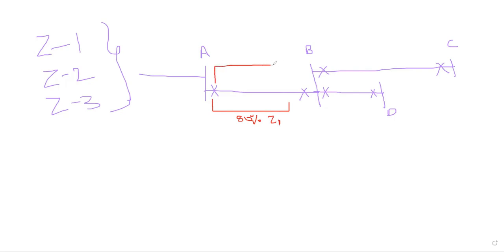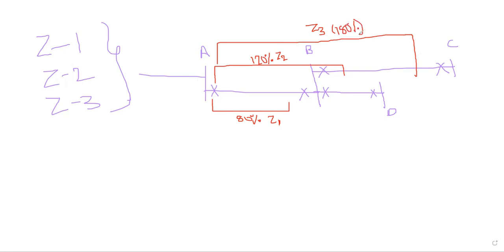And 120% of the line, the next longest line, is under Zone 2, and 180% of the line falls under Zone 3 for this relay, because it has to protect in this direction. To protect in this direction, the CT connection should be towards the protected object. So Z3 is the zone protection which is 180% of the line. Zone 1, Zone 2, Zone 3.